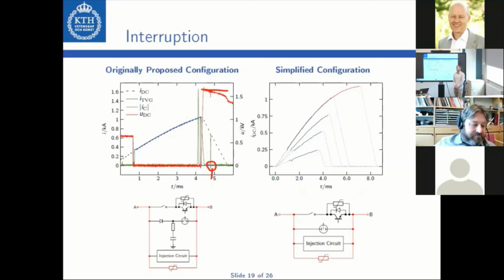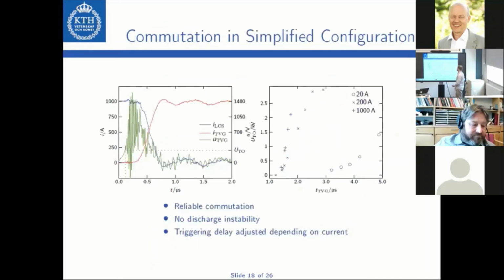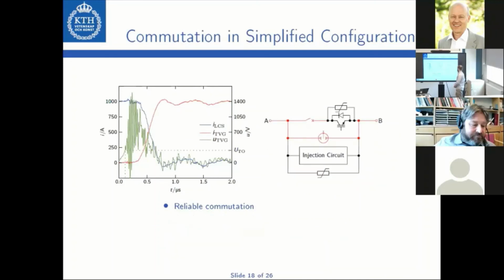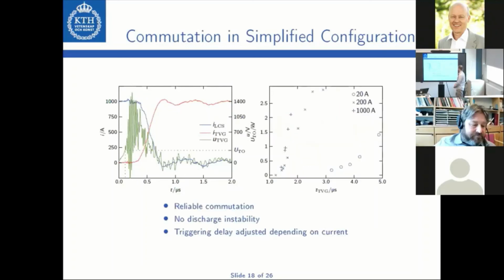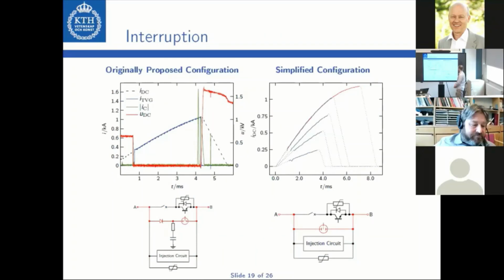But you saw some spikes before as well. Have you looked at currents in the surge arresters or maybe in the capacitor in your injection circuit, that there might be dielectric breakdowns there? Do you mean during these commutation studies or? No, during—you saw the spikes in the suppression time, so possibly there is some component that is excessively stressed, and then there is a breakdown there. Could that be the reason? I mean, it could be actually...